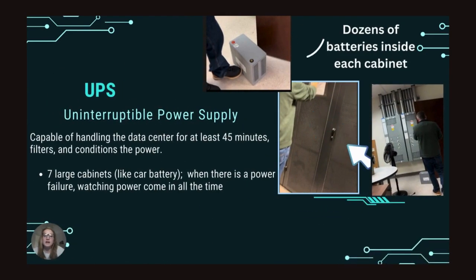So once we moved out of the main data center, we entered another room that had the uninterruptible power supply. This is the backup power supply. If there's a cut in the power connection to any of the equipment in the data center, this is the temporary backup. It's capable of handling the data center for at least 45 minutes, backing up the generator, which I'll talk about next.